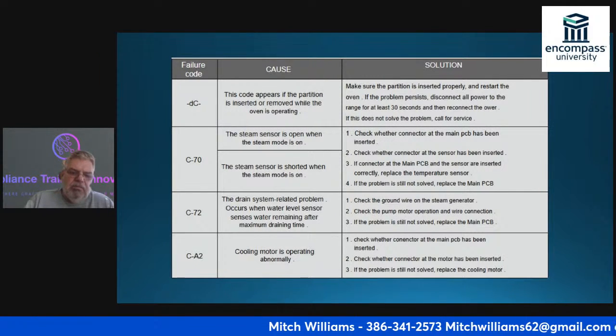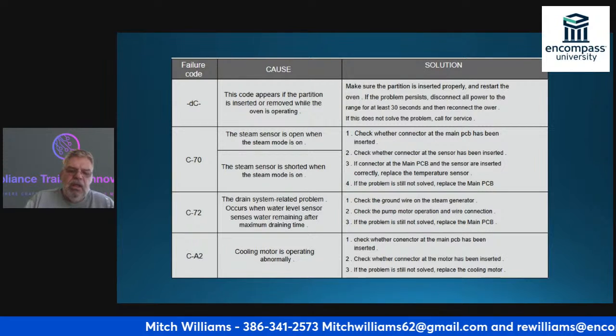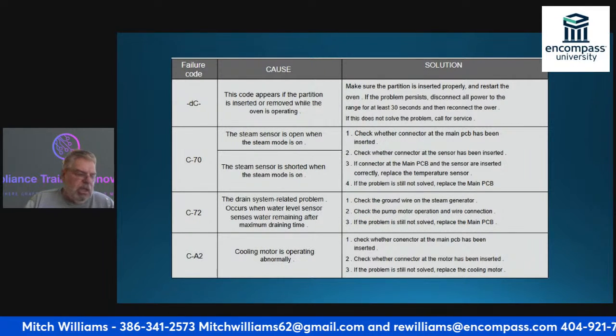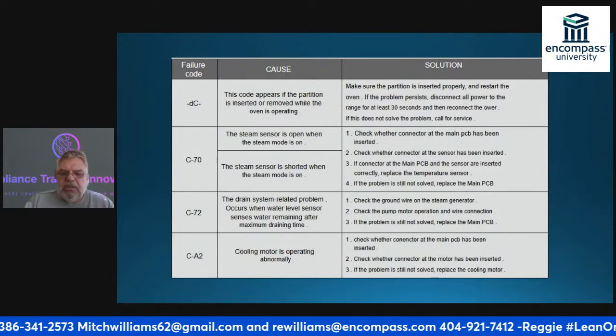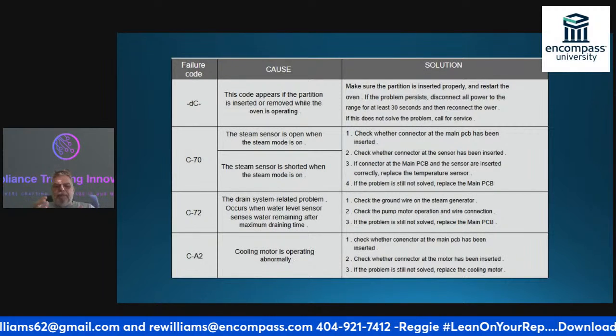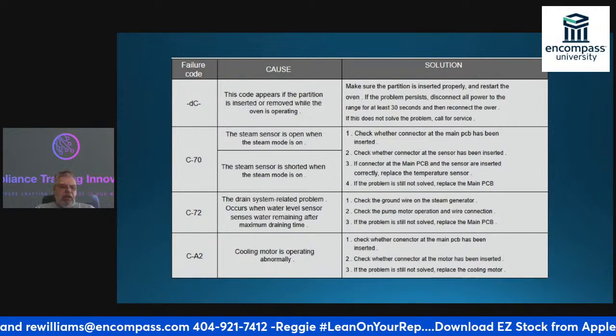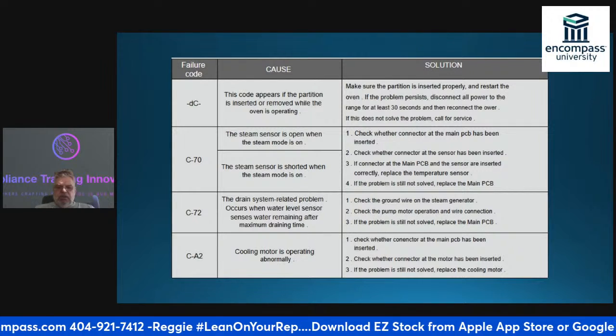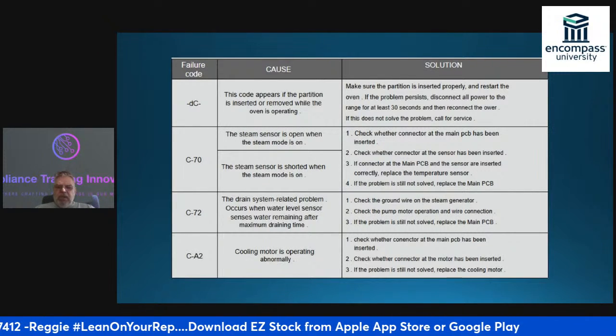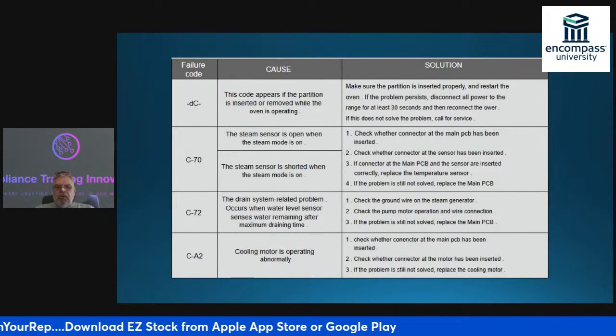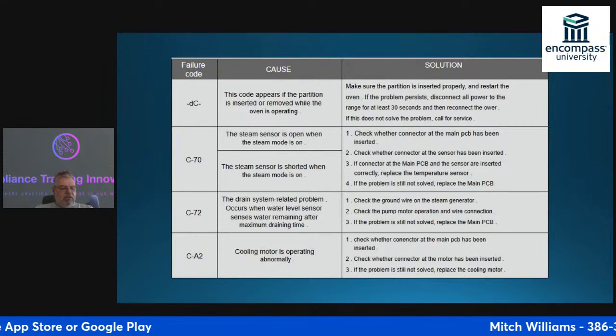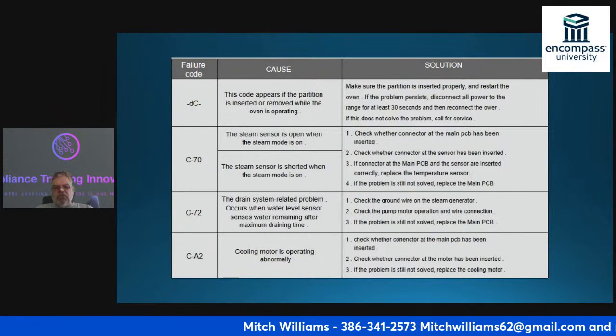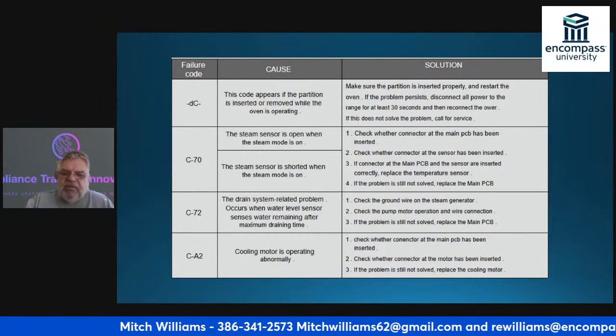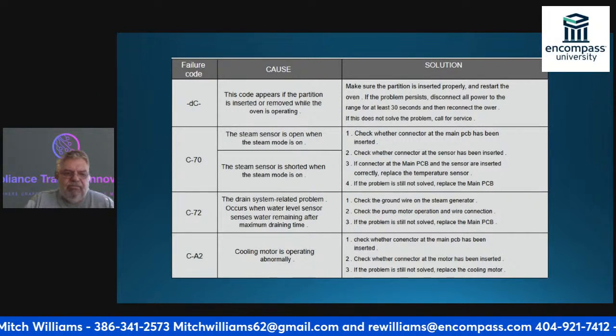Okay. If I have a CA2, our cooling motor operation is not working properly. So it tells me that I'm either going to have a main PCB connector connection that is not proper, and it could also be that the motor connector is not proper. Okay. If I have a CA2 and all of those connections are good, it means I've got a bad cooling motor itself.